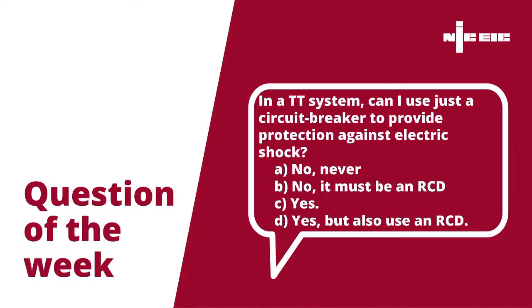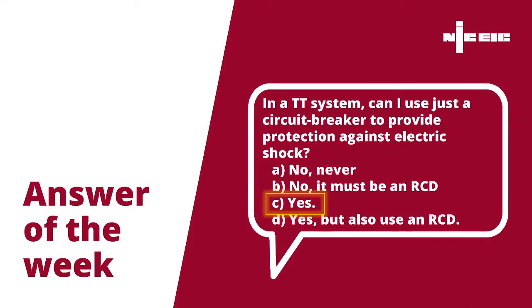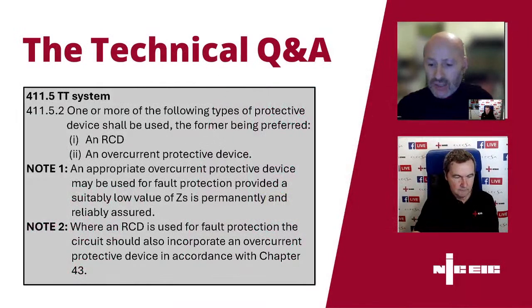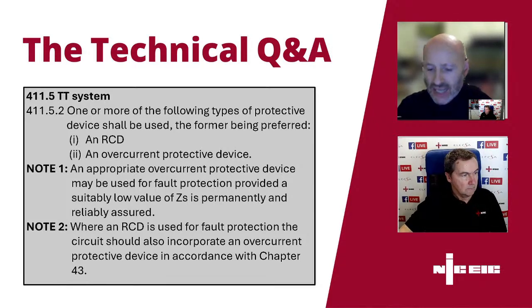So what's our thoughts on that one, Dean? Can we just use a circuit breaker for protection against electric shock? Well, drum roll, for those who are already thinking about it, the answer is C - yes, we can. There's a regulation out there, for those who want to take a note, 411.5.2, and it states that one or more of the following types of devices shall be used, the former being preferred, and it gives us two options: an RCD, and secondly an overcurrent protective device. So the answer is yes.